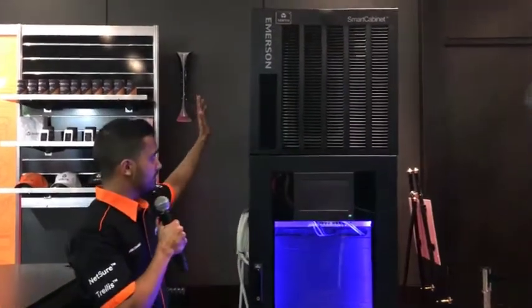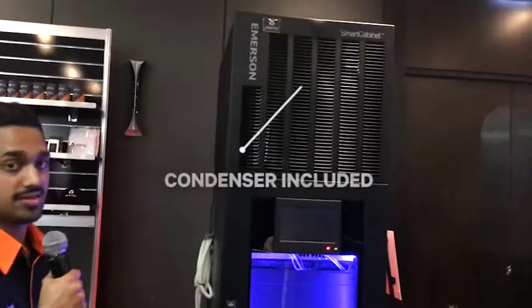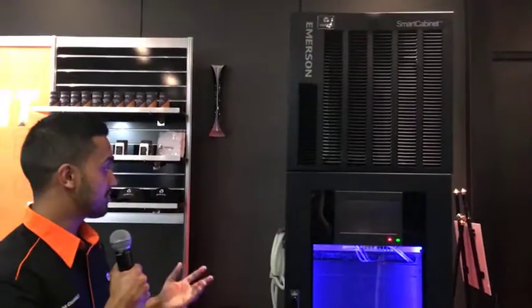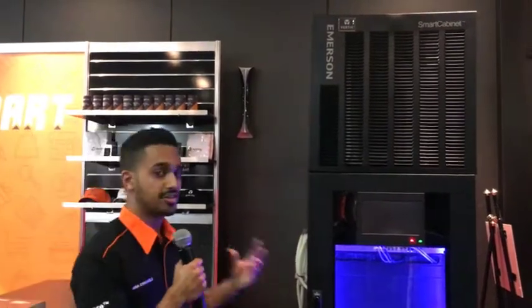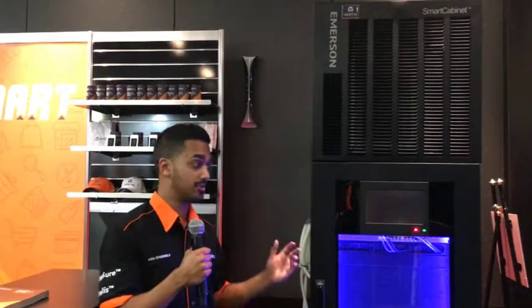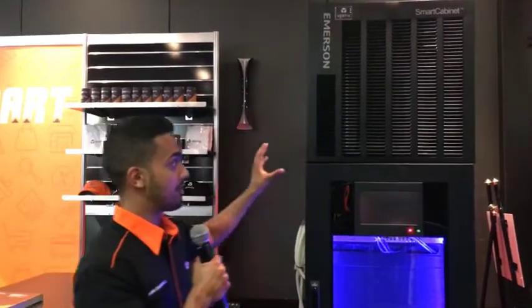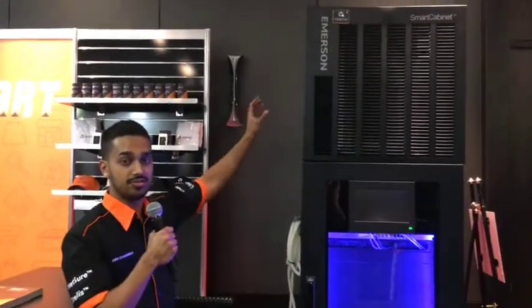The biggest thing about this smart cabinet being integrated is that the condenser is part of the single cabinet or unit. This means there's no longer an external or outdoor condenser — perfect for those customers who, traditionally in a retail store, wouldn't have space or a balcony for an outdoor unit. The hot air can simply be ejected out the side and ducted into the ceiling.